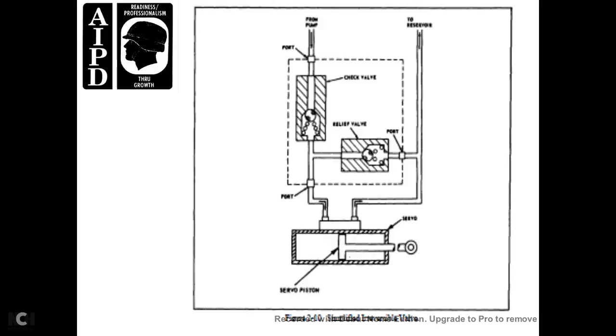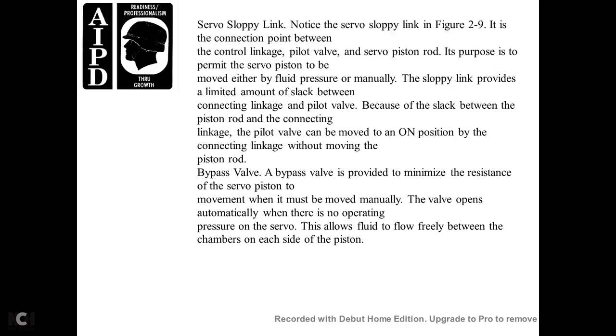Servo Sloppy Link. The sloppy link in figure 2-9 is the connection point between the control linkage pilot valve and the servo piston rod. Its purpose is to permit the servo piston to be moved either by fluid pressure or manually. The sloppy link provides a limited amount of slack between the connection linkage and pilot valve. With this slack between the piston rod and connection rod, the pilot valve can be moved to an ON position by the connecting linkage without moving the piston rod.